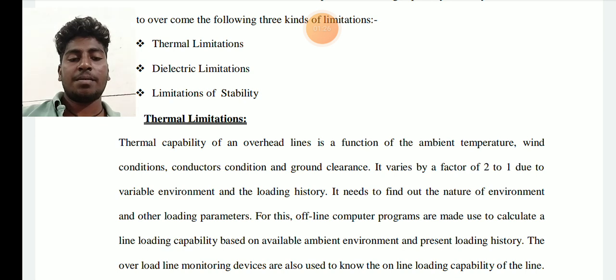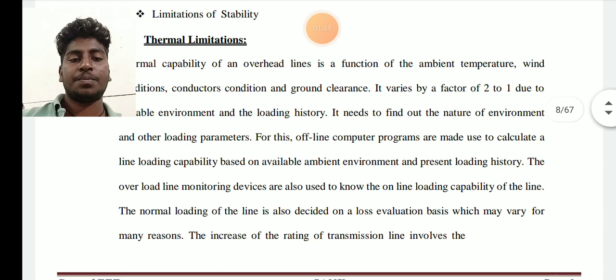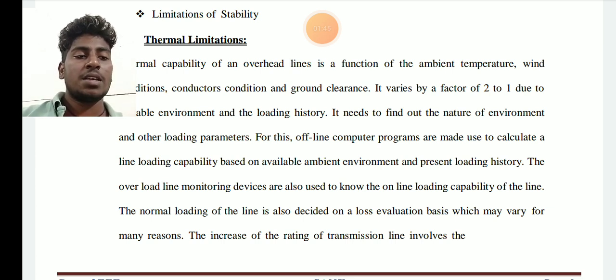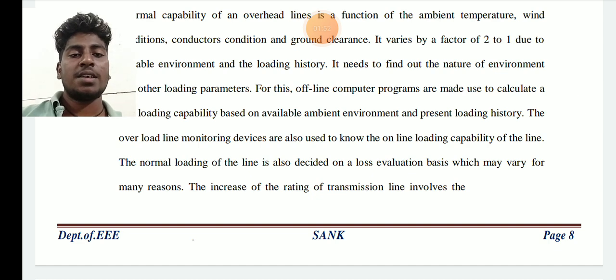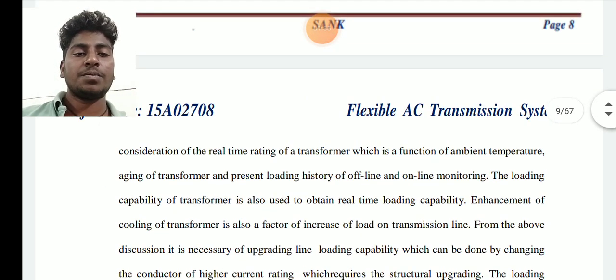Overload line monitoring devices are also used to know the online loading capability of the line. The normal loading of the line is also decided on a loss evaluation basis, which may vary for many reasons. The real-time rating of a transformer, which is a function of ambient temperature and the present loading history, can be obtained offline, and online monitoring of the loading capability of the transformer is also used to obtain the real-time loading capability.